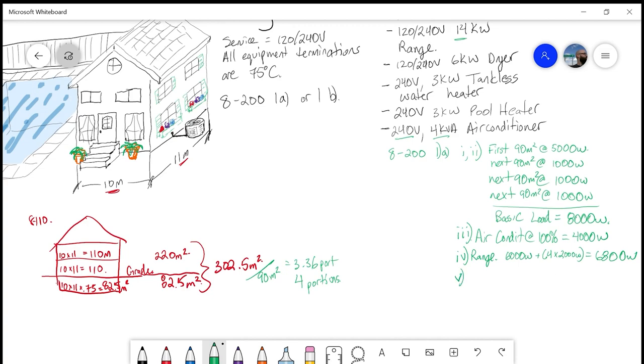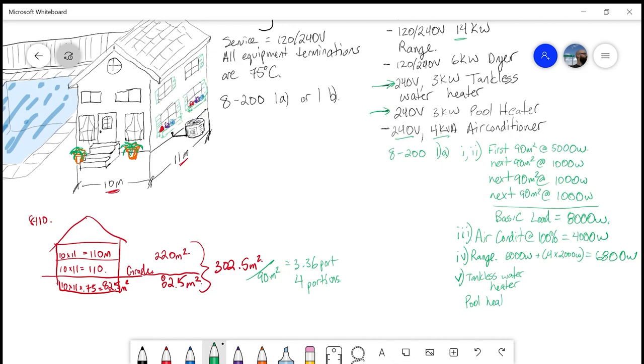Then we look at item v, which is all of our loads like tankless water heaters, pool heaters, hot tub heaters, things like that. We have this 240 volt, 3 kW tankless water heater. Watch for the question throwing in a hot water tank. Two very different things. We also have this 240 volt, 3 kW pool heater. Both of these, according to item v, go in at 100%. Our tankless water heater is 3,000 and our pool heater is also 3,000.